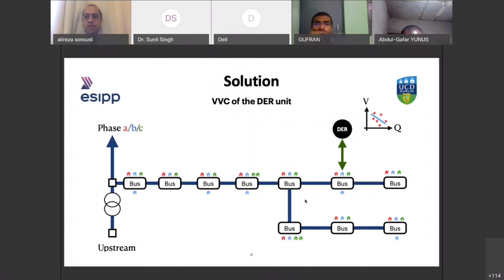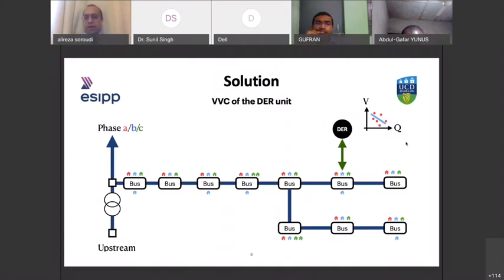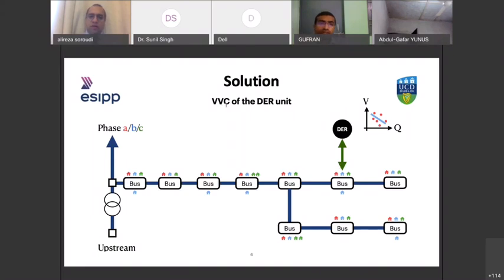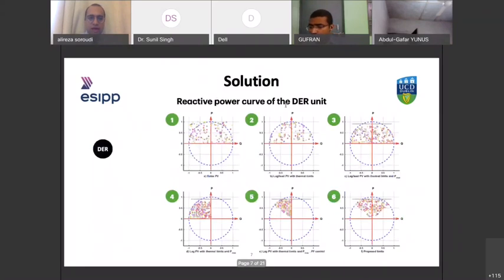We want to reduce the active losses, reduce voltage profile violations, and have a flat voltage profile. A volt-VAR curve is a simplistic way to achieve this. The idea is: can we sense the voltage at the connection point and find the best setting for the reactive power Q of these technologies? This is called the VVC or volt-VAR curve of the DER unit, and these curves are optimized for some objective functions.